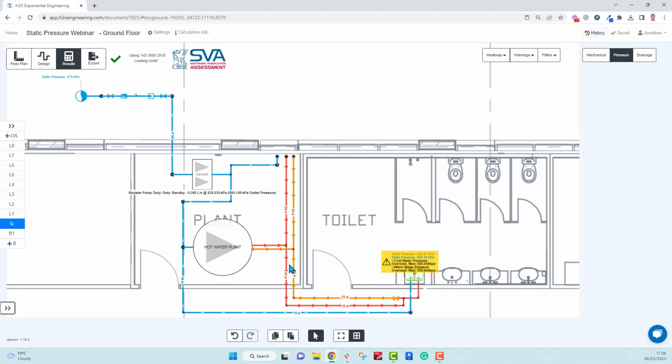The next tricky thing is you cannot put pressure reduction valves on hot water recirculation systems. This is a really complex subject and we do have a blog on it. So if you search our website for balancing recirculation systems, hot water, you will find it. But essentially, putting pressure reduction valves on some of the circuits will completely unbalance the system and it won't work. So the tricky part to this is, where do we put the valves? Essentially, on a cold water system, you can put them anywhere. But on a hot water flow and return system, on the inlet to the plant is a good location, on the cold supply. But if that isn't going to be sufficient, you will need to put them on the branches where the water is not recirculating.